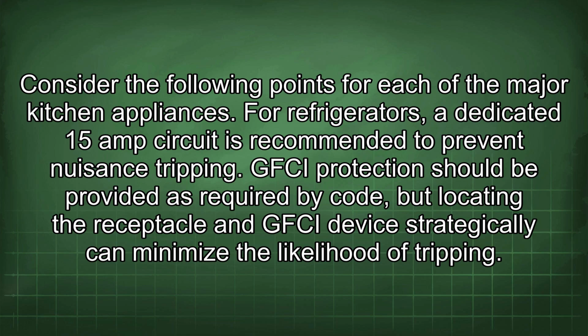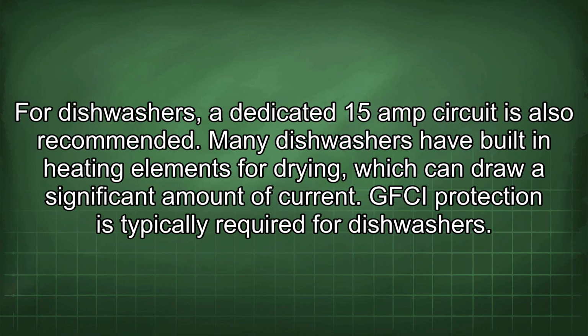For refrigerators, a dedicated 15-amp circuit is recommended to prevent nuisance tripping. GFCI protection should be provided as required by code, but locating the receptacle and GFCI device strategically can minimize the likelihood of tripping. For dishwashers, the dedicated 15-amp circuit is also recommended. Many dishwashers have built-in heating elements for drying, which can draw a significant amount of current. GFCI protection is typically required for dishwashers.